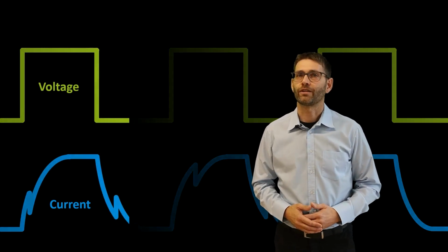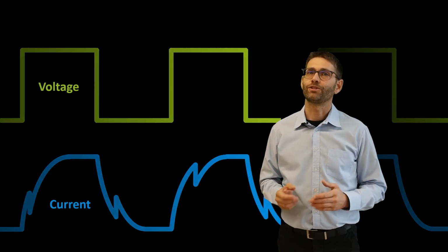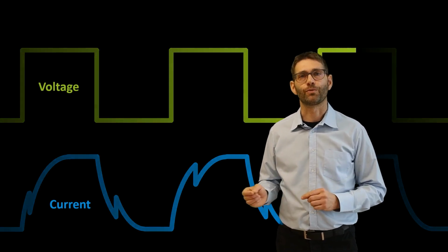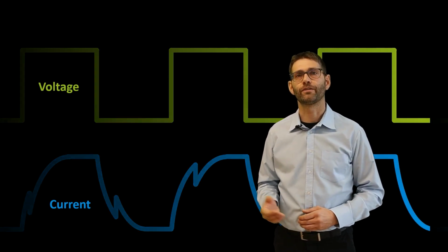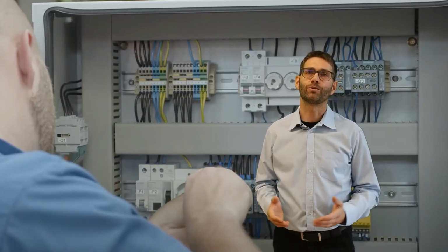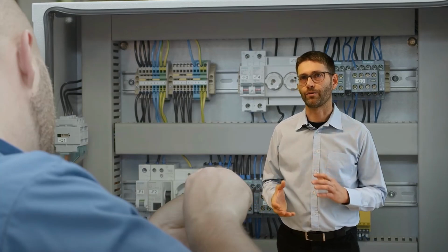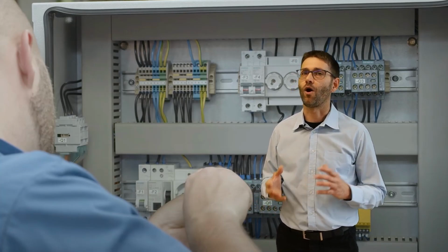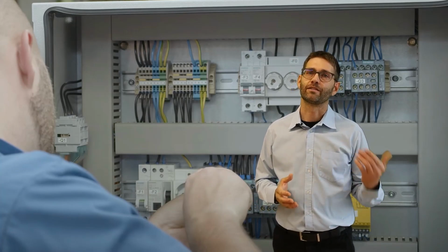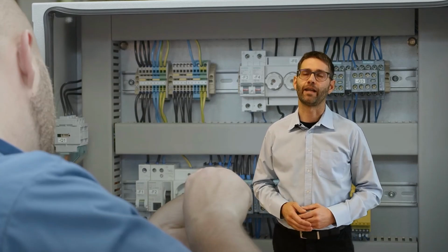The robo brake checker is connected directly into the brake supply without additional sensors and monitors the brake. The actuator itself becomes a kind of sensor. Since the robo brake checker module operates from the control cabinet in a protected environment, ambient conditions on the brake, such as dust, dirt and temperature, have no influence on the reliable function.